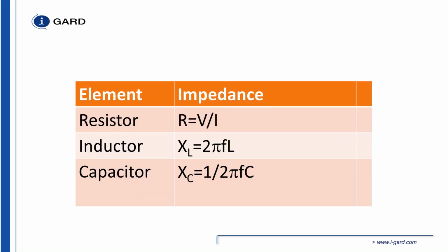So we used to use a DC voltage and current injected upon the system. Now we're using a frequency dependent signal. So you can see that the resistor doesn't change with the impedance or the frequency. It's frequency independent, shall we say. The inductance is going to increase the impedance as the frequency elevates, and the capacitance is going to decrease the impedance when you have a higher frequency. So because the capacitance is in series with the inductance, you're going to probably end up with a high level.